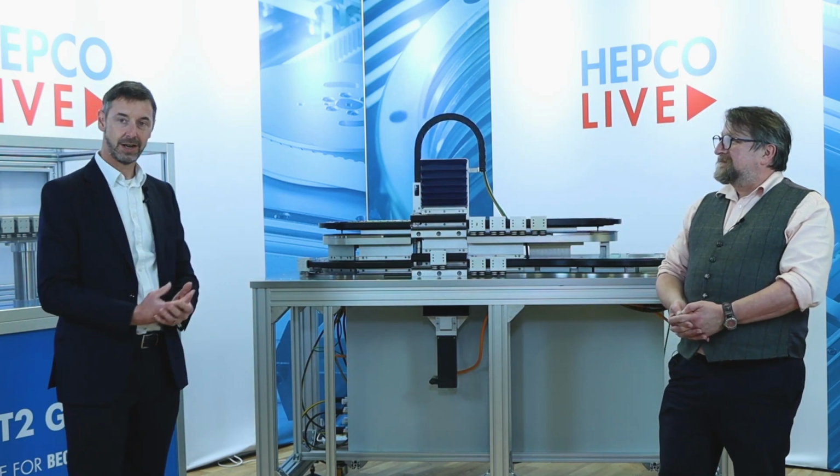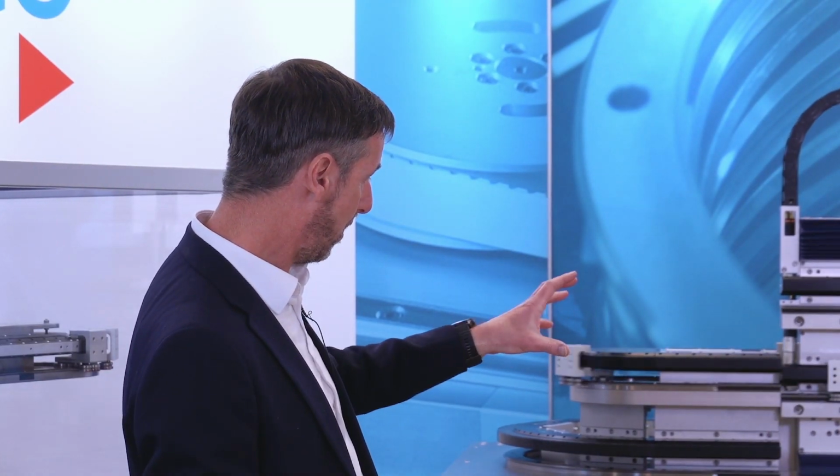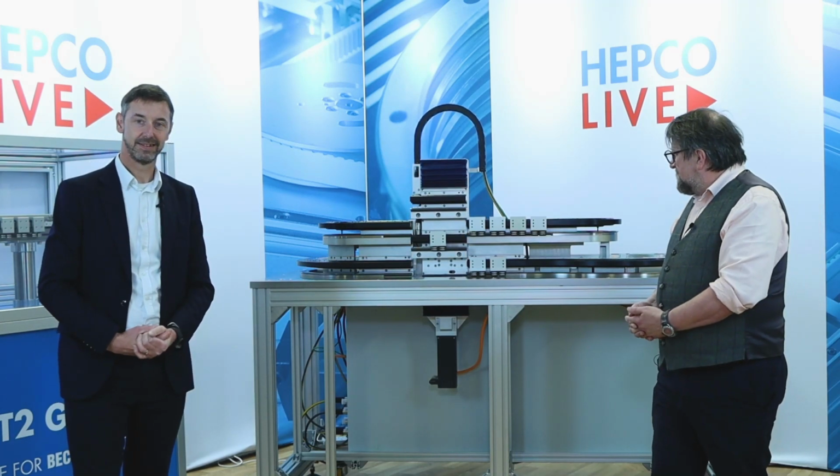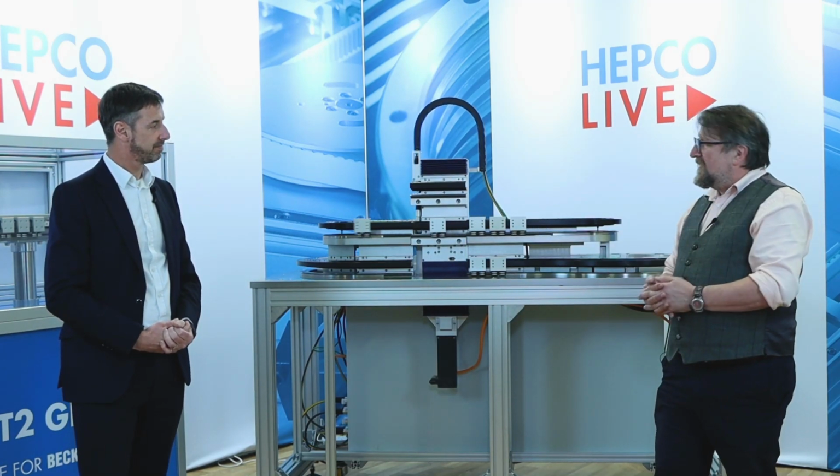Yes. Okay, and of course, I know when a machine is running for an extended period, you get things like heat build-up, and you need to maintain a very high level of accuracy on that transition. How do you realistically do that? Well, we've got two methods. There's one that's built in, which is the position of the encoder and the encoder strip. So it's neatly balanced and enclosed, so any thermal variations have the minimum effect on the position. And the other one is we do actually monitor temperature. So temperature extremes can be accommodated within the software for the track management.